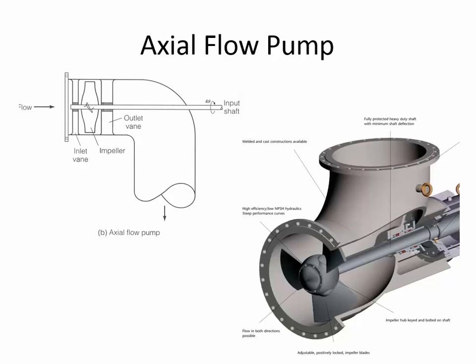Okay, related is an axial flow pump. And here you can see the difference with an axial flow pump is that the motor is going to be some distance away from the impeller. And so the energy is transferred through a shaft. And usually in the case of an axial flow pump, what would be common here is to have the motor at the surface. Let's say you're pumping water from an aquifer, which is deep underground. This allows you to have the motor at the surface, and then the shaft goes down deep underground until it gets to the water level, and then you can have the impeller beneath the water line. And that makes it easier to prime the pump when it's just first getting started than if the impeller is up at ground surface. It's really hard for a pump to suck air up through the casing till it finally fills with water. And so axial flow pumps, the advantage here is it just allows you to separate the location of the motor and the impeller.